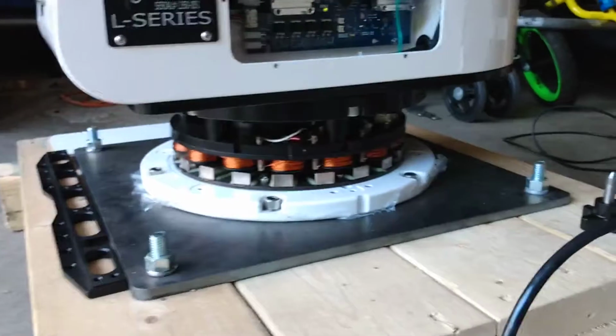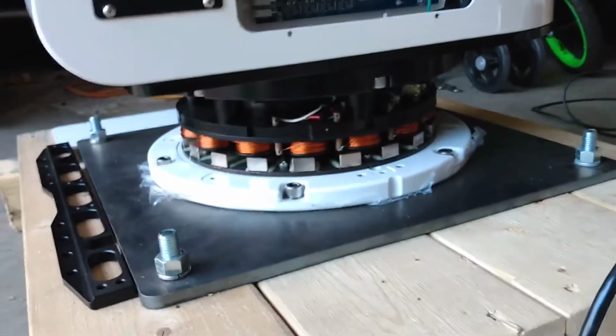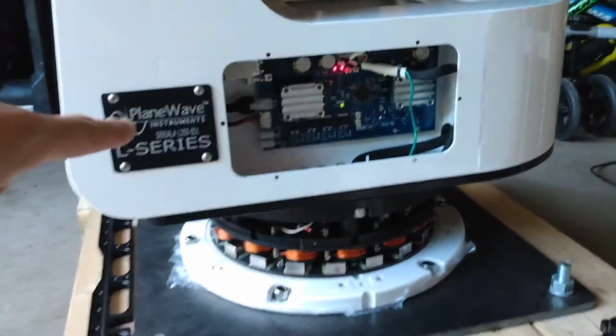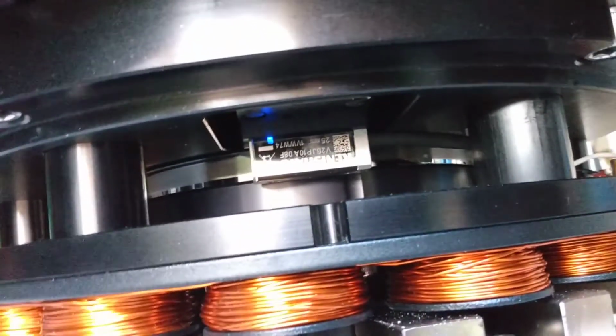So once those are off, you can see the inside of the motor, and we want to locate the encoder read head on this motor. In this case, you take the side facing you with the serial number plate and come 90 degrees over in this direction, and the read head is right there. You can see the blue status LED on there, which shows normal operation.